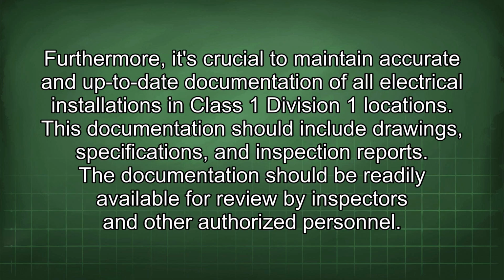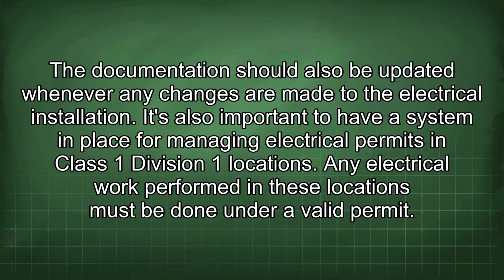Furthermore, it's crucial to maintain accurate and up-to-date documentation of all electrical installations in Class 1 Division 1 locations. This documentation should include drawings, specifications, and inspection reports. The documentation should be readily available for review by inspectors and other authorized personnel. The documentation should also be updated whenever any changes are made to the electrical installation.